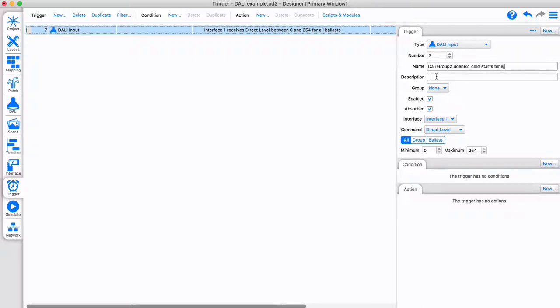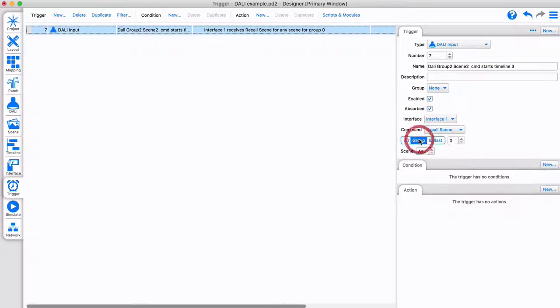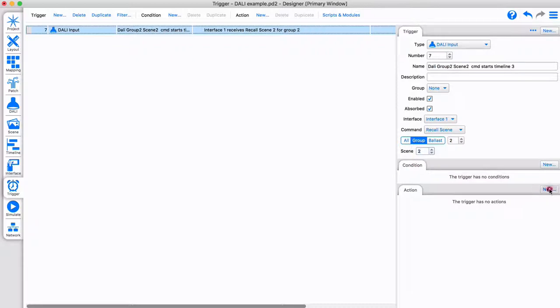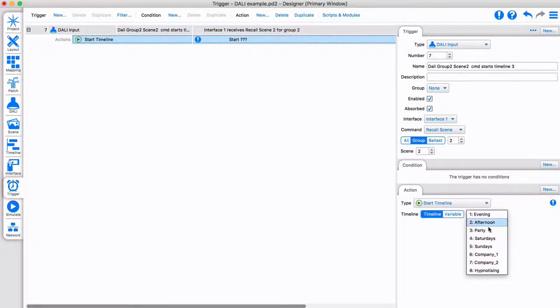Listening is useful if a Pharos product is acting as a bridge to connect a DALI system with a Pharos DMX system. In this example, upon hearing a certain DALI command, there is a recall of scene 2 on group 2. Pharos trigger can start a timeline or scene to control the DMX fixtures or provide any other action.